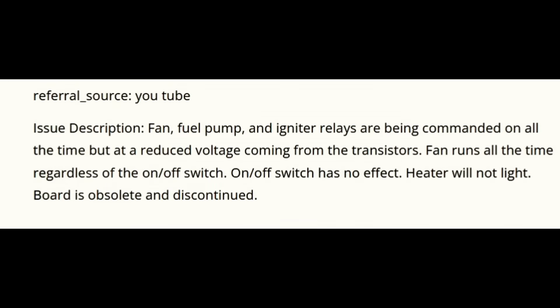Let's see what the customer wrote. Referral source: YouTube. Description: Fan, fuel pump, and igniter relays are being commanded on all the time, but at a reduced voltage coming from the transistors. Fan runs all the time, regardless of the on-off switch. On-off switch has no effect. Heater will not light. Board is obsolete and discontinued.